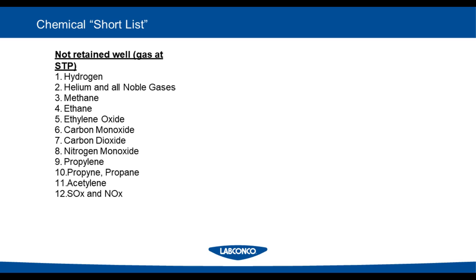Now the good news is they're not commonly used in laboratories. Some of these aren't even hazardous, not in the concentration that would be released into the laboratory, but some of them most certainly are. So if you're using any of these, and you're using them in higher volumes, it's probably a no-go for a filtered fume hood. If you're using them in lower volumes, and I know higher and lower is always a difficult subject. What is high, what is low, what is a lot, what is a little, what is medium? Really depends on the frequency and the quantity used. I like to think of if it's less than 200 milliliters a couple times a month, I think we've got a solution for you.